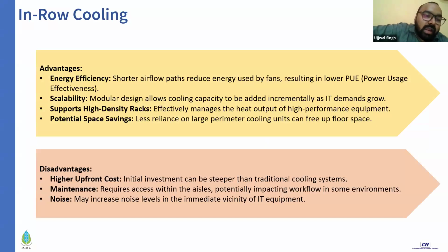So as I said, the advantages are energy efficiency and scalability. As you get more servers, you can simply place one more unit adjacent to them, and you'll be able to manage it very easily. For rack densities in cold aisle systems, I wouldn't recommend going beyond 15 or 20 kilowatts, which is already on the higher side for cold and hot aisle containment systems. If you go beyond 15 kilowatts per rack, I'd suggest switching to in-row cooling or other cooling infrastructure technologies.